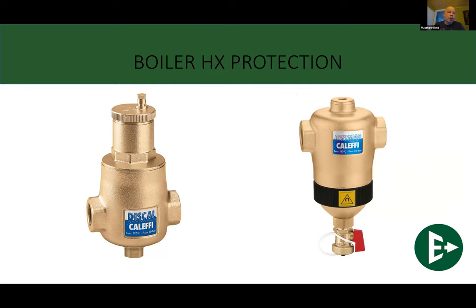I just do recommend to make sure that you clean them as best as you possibly can. And to be 100% honest, there is no substitute for a hard bristle brush to clean at least the water tube heat exchanger. I saw one guy take a hard bristled toilet brush and attach it to a drill and use that to clean around the inside of that heat exchanger. And it worked like crazy. The hard bristle brush is soft enough. It's not going to damage the actual stainless steel, but it will get into those nooks and crannies to make sure that we get these things cleaned out as best as we possibly can.